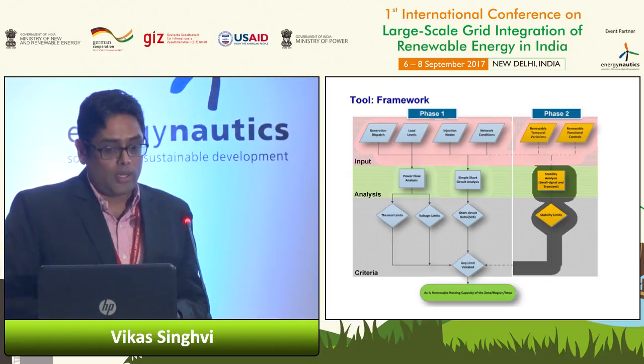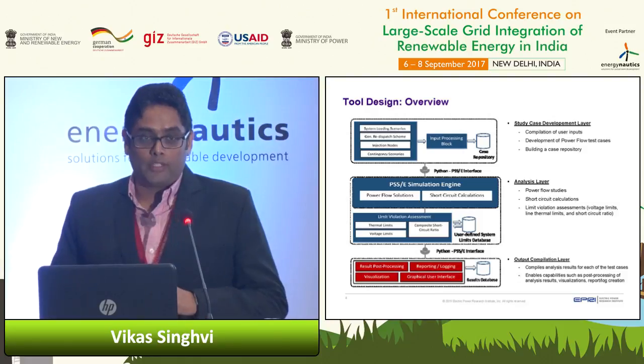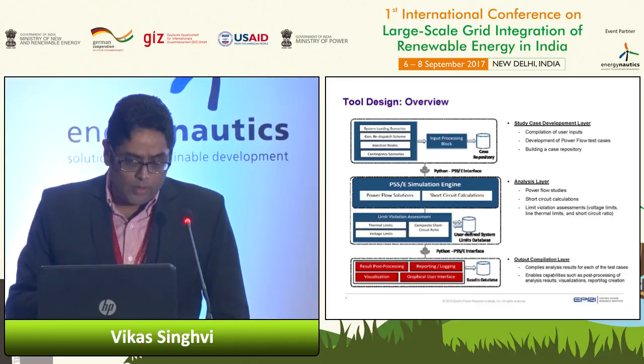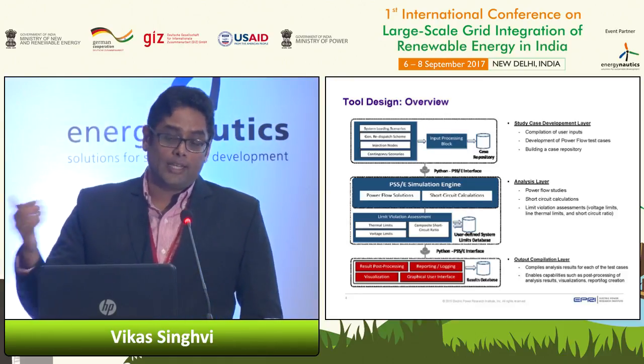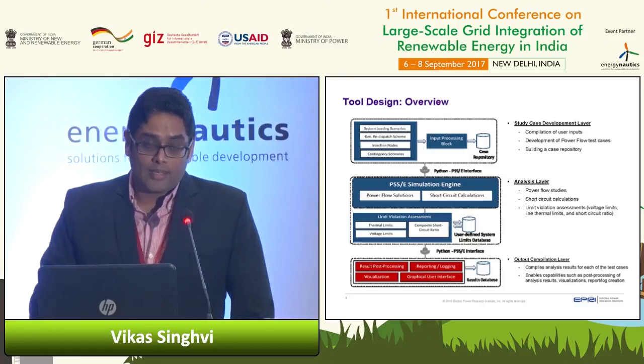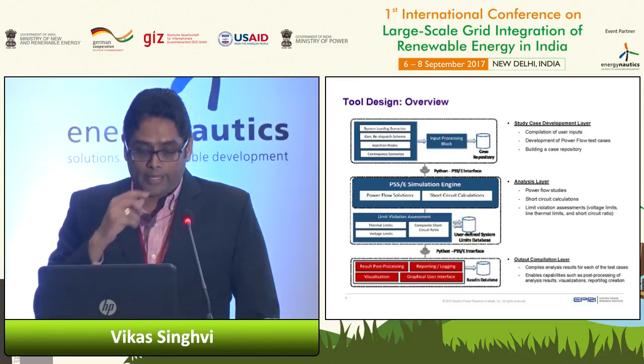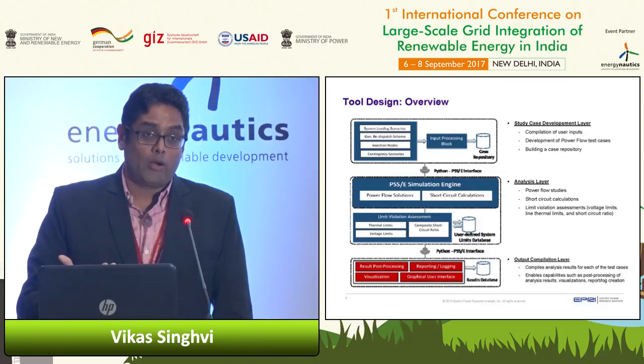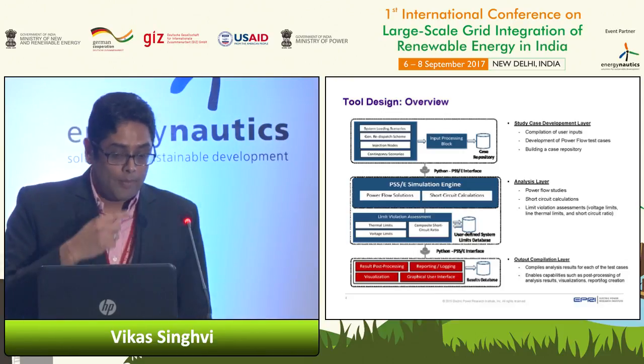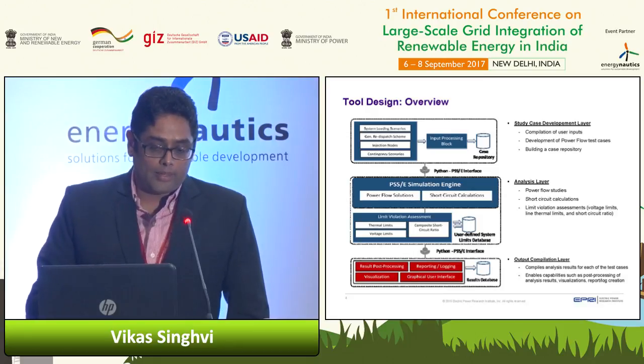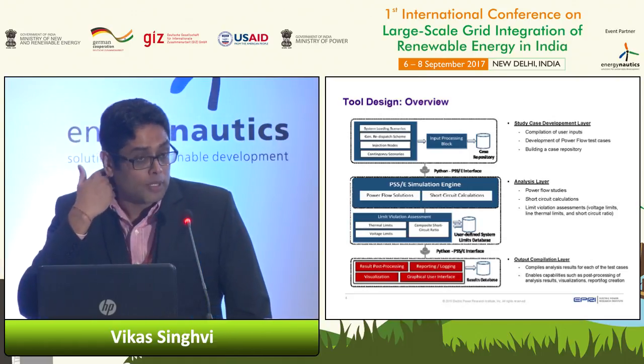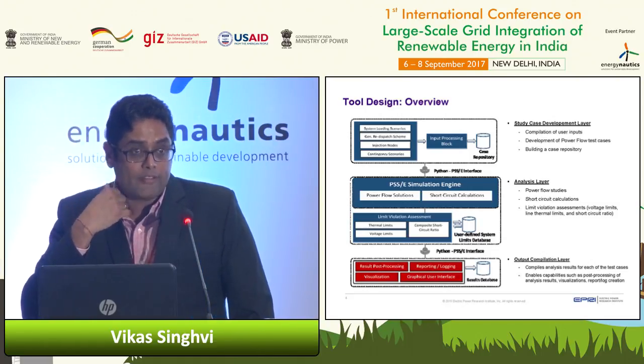To give a quick 10,000-foot overview of the tool design, it is basically divided into three layers. The first layer is where we develop all these cases. The tool can take multiple inputs — different redispatch scenarios, load levels, your winter peak case, summer peak case, or shoulder levels. It can also take planned and unplanned outages and develop this case repository. Once you have a case repository, the PSSE engine goes through each and every case and, based on the provided criteria for voltage, thermal, and short circuit, it comes up with the hosting capacity for each case.